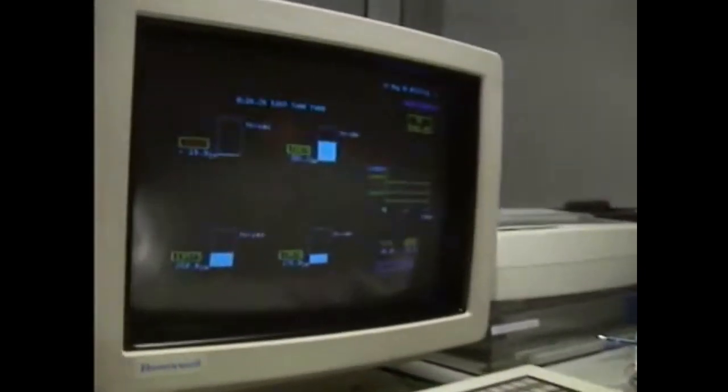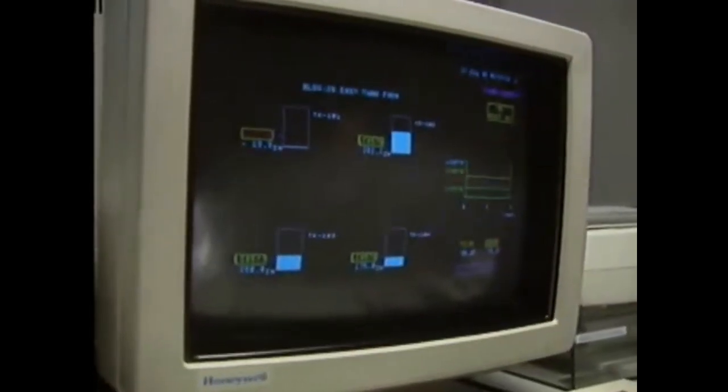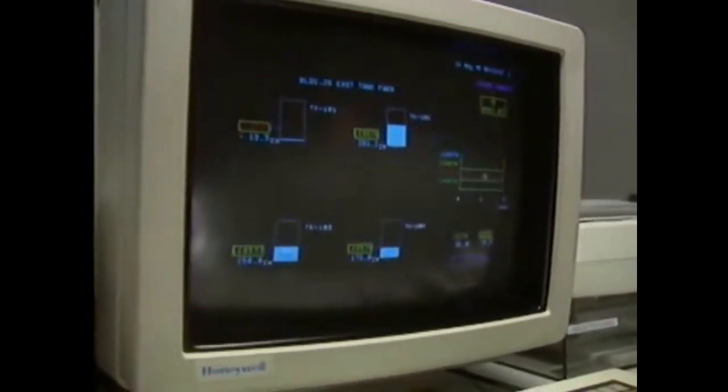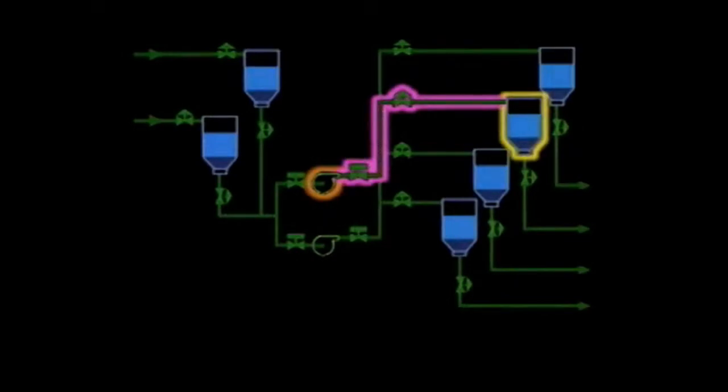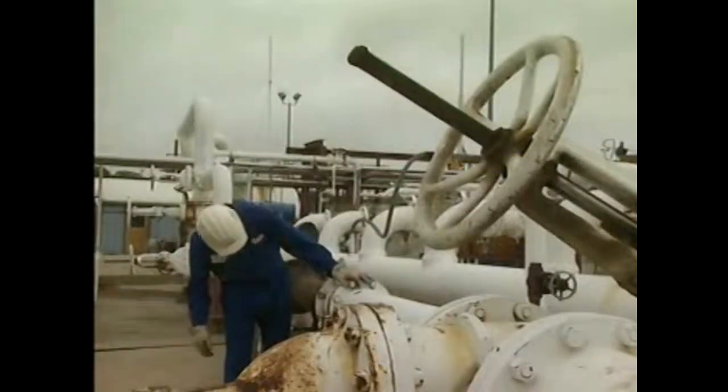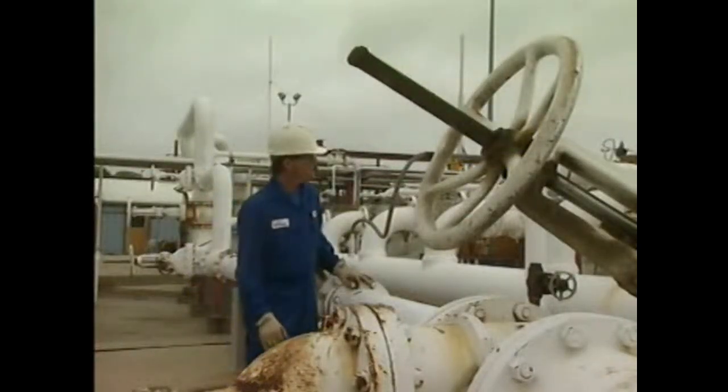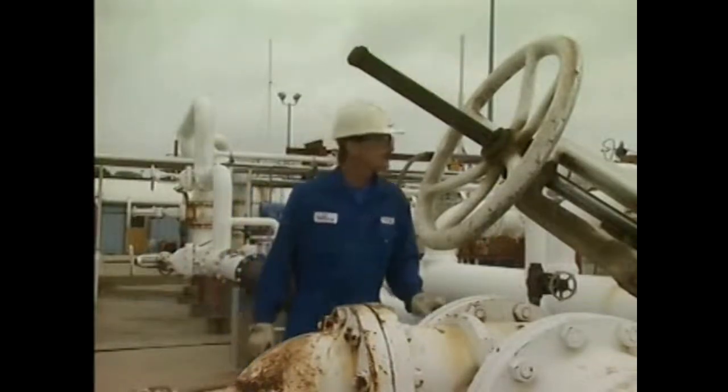They know that without proper level indication in the process feed tank, there is a possibility of a spill. At this point, the control room operator decides to use the bracketing method to narrow down the cause of the problem. He starts by bracketing the transfer system into 3 parts: the transfer pump, the piping, and the process feed tank. The control room operator has the outside operator check the piping for any problems.